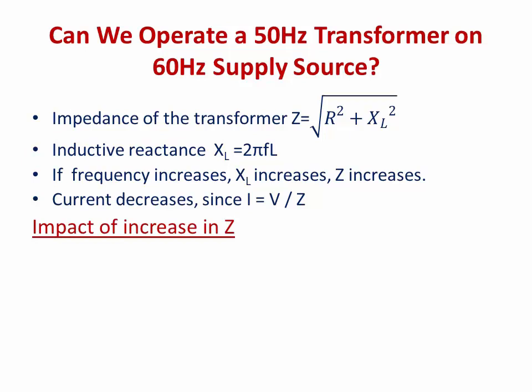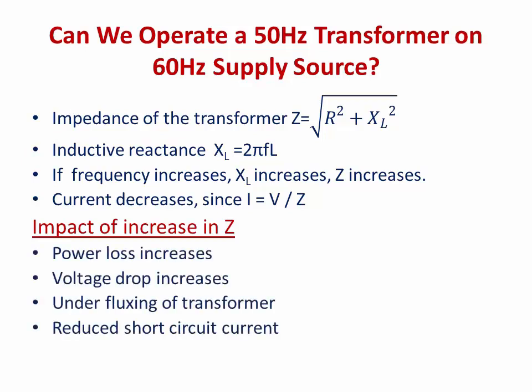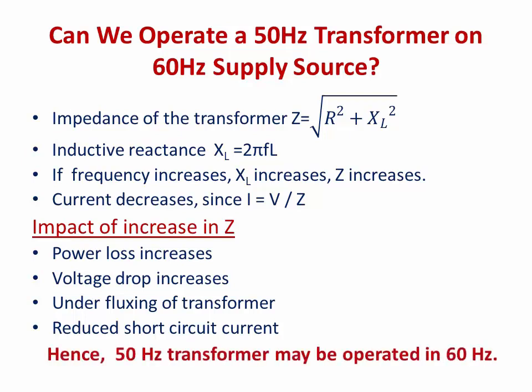Let us analyze the impact of increasing impedance. There will be power loss, voltage drop increases, under-fluxing in the transformer, and reduced short circuit current. Considering power loss and voltage drop, the increment is not going to have a great impact. Under-fluxing means we are operating the transformer in a normal operating region. Reducing short circuit current is a great advantage. Hence, a 50 Hz transformer may be operated on a 60 Hz supply without any difficulty.